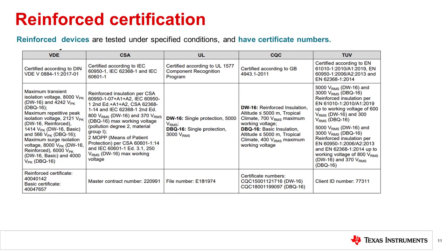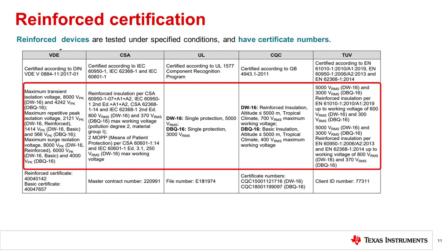Are all 5 kV isolators reinforced isolators? While most reinforced digital isolators have a rating of 5 kV or higher, isolators can be rated for 5 kV isolation protection and not necessarily be reinforced isolators. In order to achieve a reinforced rating, isolators must pass the surge test at 10 kV and must also maintain package creepage and clearance requirements, conditions for repetitive peak voltage, climate, and material and pollution groups. All conditions of test must be met in order to achieve the VDE certification.